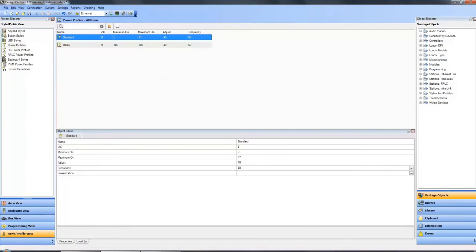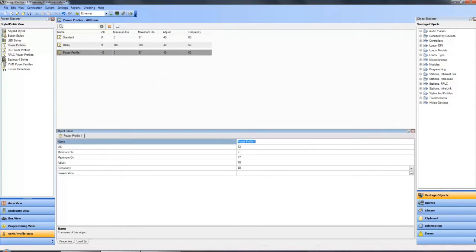Step one, within the style profile view, we create a new power profile. There are three types of power profiles. Default for forward or reverse phase dimmer loads, known simply as power profile. DC profile for 0 to 10 dimmer loads. And PWM power profiles for PWM dimmer loads. Once we select the correct profile type, we double click to create a new profile and rename it so as to represent the applicable fixture.